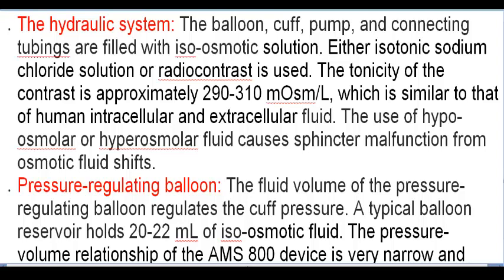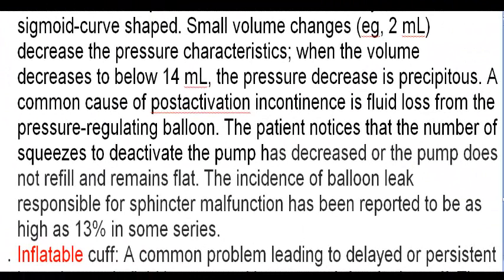Pressure regulating balloon. The fluid volume of the pressure regulating balloon regulates the cuff pressure. A typical balloon reservoir holds 20 to 22 ml of isoosmotic fluid. The pressure-volume relationship of the AMS 800 device is very narrow and sigmoid curve-shaped. Small volume changes, e.g., 2 ml, decrease the pressure characteristics. When the volume decreases to below 14 ml, the pressure decrease is precipitous.